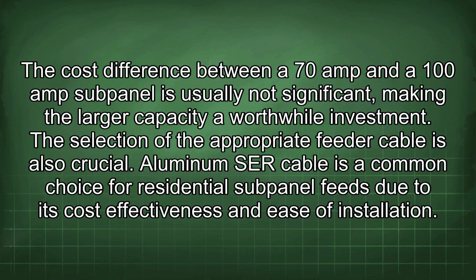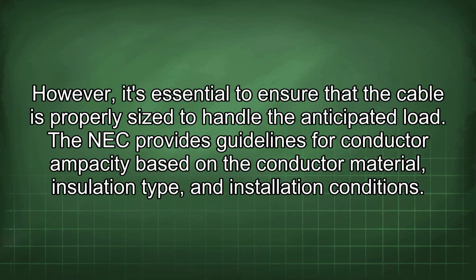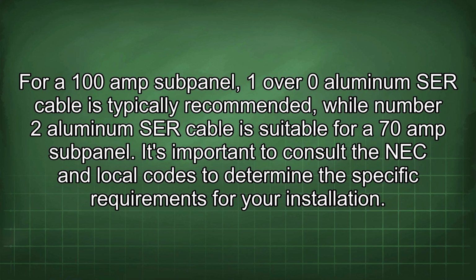Aluminum SER cable is a common choice for residential subpanel feeds due to its cost-effectiveness and ease of installation. However, it's essential to ensure that the cable is properly sized to handle the anticipated load. The NEC provides guidelines for conductor ampacity based on the conductor material, insulation type, and installation conditions. For a 100 amp subpanel, 1/0 aluminum SER cable is typically recommended, while number 2 aluminum SER cable is suitable for a 70 amp subpanel. It's important to consult the NEC and local codes to determine the specific requirements for your installation.